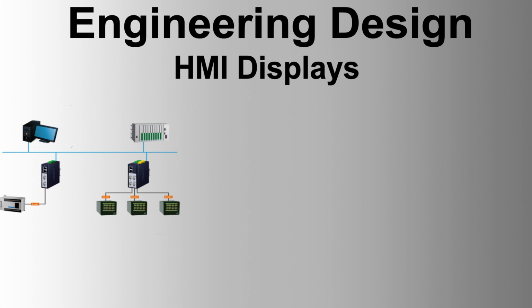Trend window, shows trends of instruments. Message Help window, provides operational assistance. Short duration trends should be used within schematic graphics for key process parameters. Controller parameters displayed in graphics should be limited to PVs at overview levels and may include SP, output, and modes at detailed levels to assist operators. By following these guidelines, the HMI design ensures a consistent, efficient, and user-friendly interface for operators and other users.